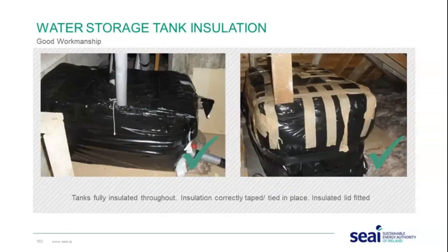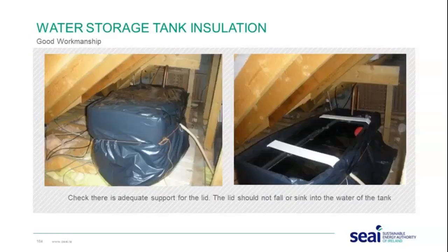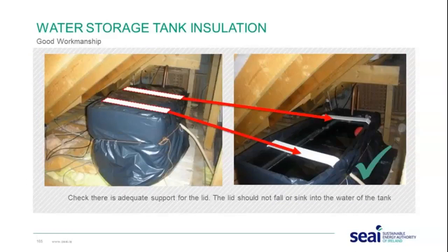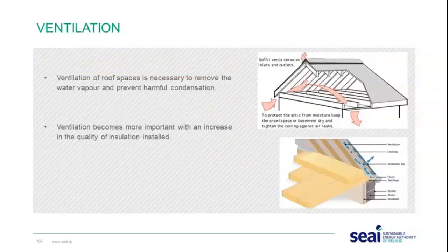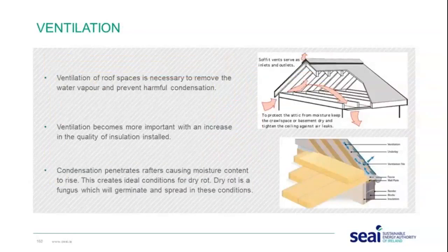Poor workmanship examples show tank insulation not held in place and no lid fitted. Good workmanship means tanks are fully insulated throughout, insulation is correctly taped and tied in place, and insulation lids are fitted. A good installation example shows the contractor installing supports for the lid to prevent the insulation from weighing down on the ball valve — correct supports for the lid can prevent a callback to fix a ball valve overflowing.